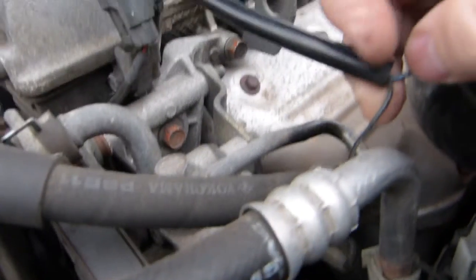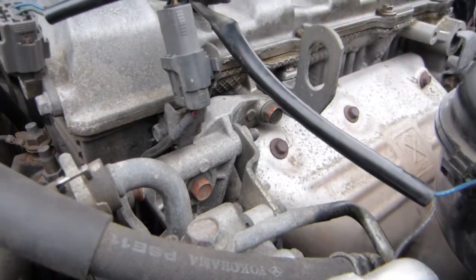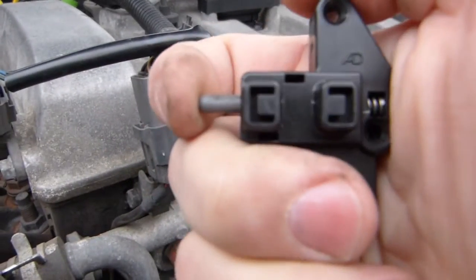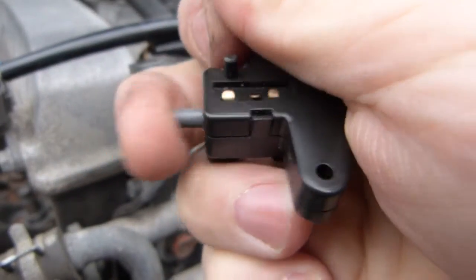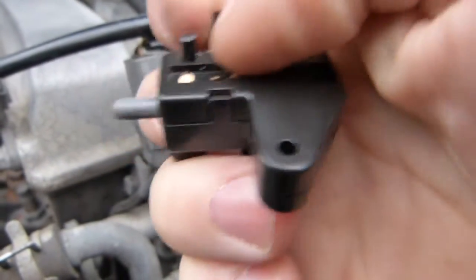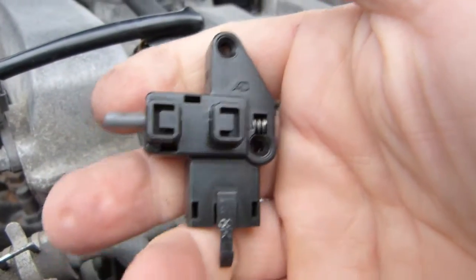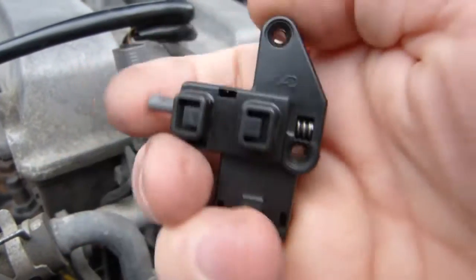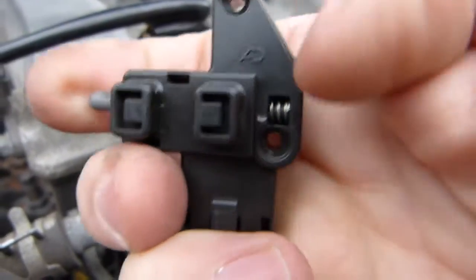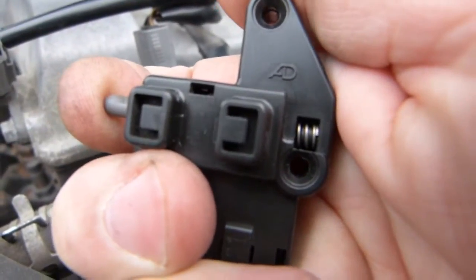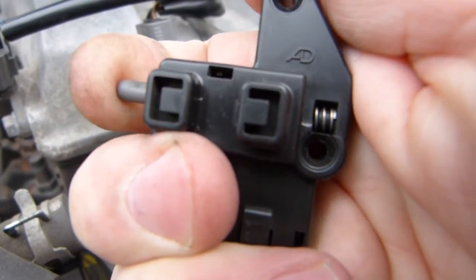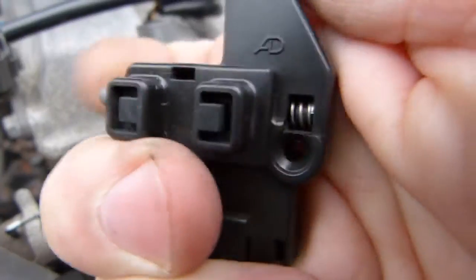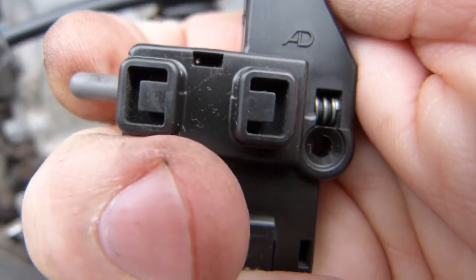If you follow this black jacketing, you'll see two single wires exiting from it, both leading to a simple mechanical switch. By mechanical switch, I mean something like this. On a mechanical switch, typically there's a plunger, and displacement on the plunger opens or closes a circuit depending on how it's wired up. The plunger's displacement is typically against a spring. You can see that spring being compressed when displacement is produced, and then the plunger returns to its original position.